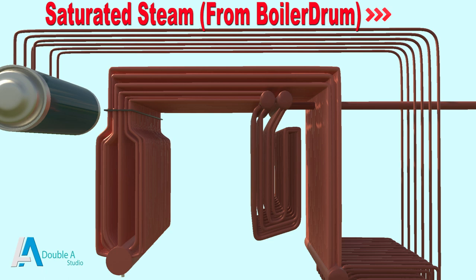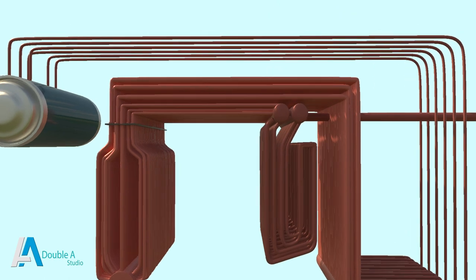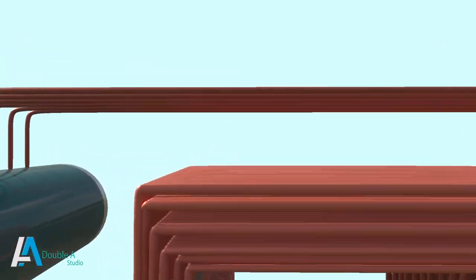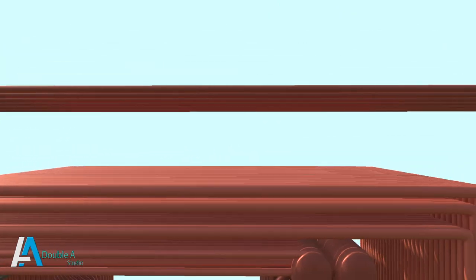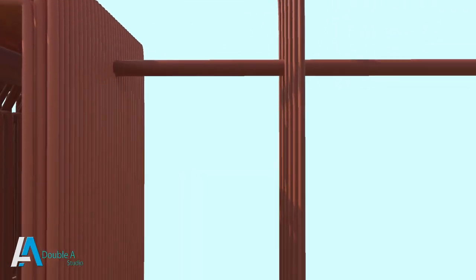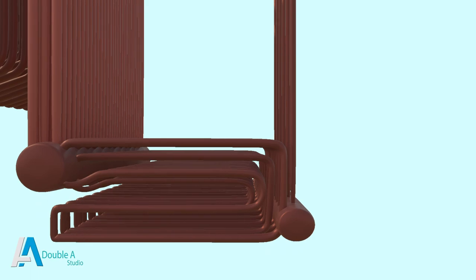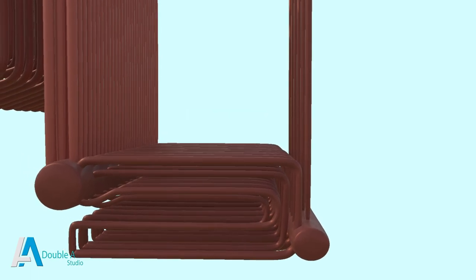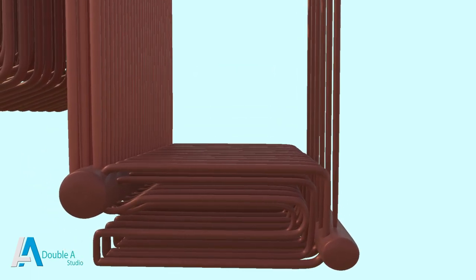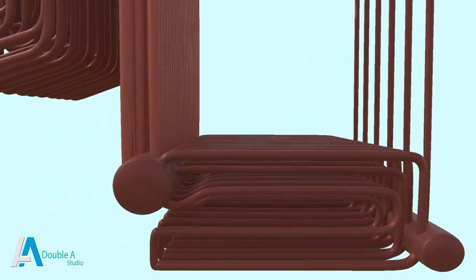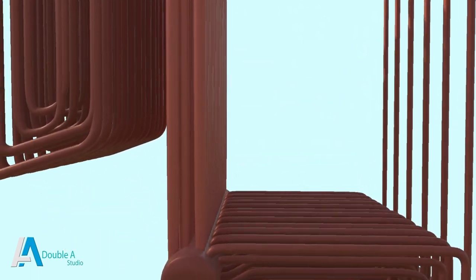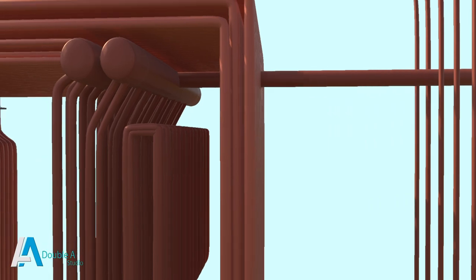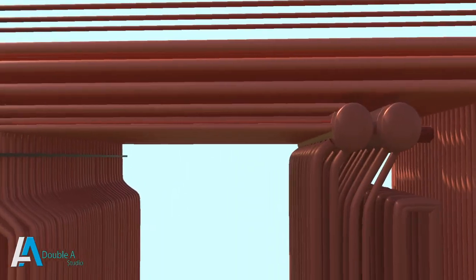The saturated steam that comes out of the boiler drum is passed through various superheaters. These are a set of tubes placed in the path of flue gases where saturated steam is further heated by the hot flue gases and gets converted into superheated steam.